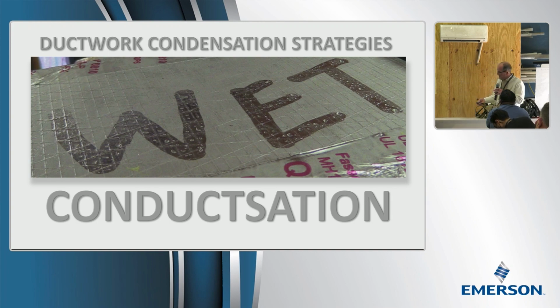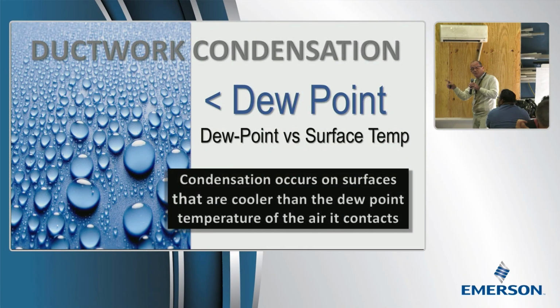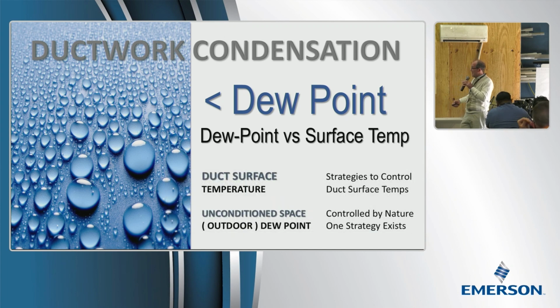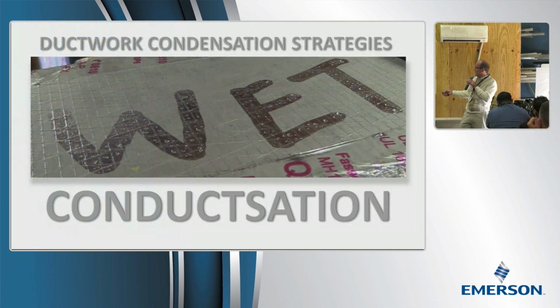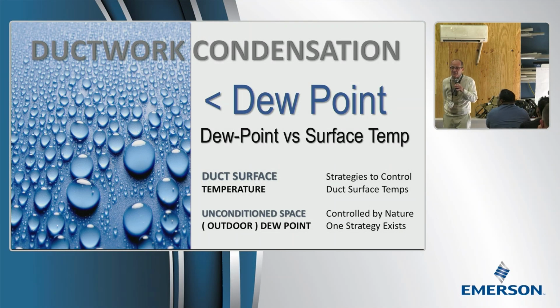This course is all about the dew point versus the surface temperature. We're going to evaluate all kinds of strategies for controlling the surface temperature, because there's so little we can do to control the dew point. What's the strategy to control the dew point? Don't put it outside, don't put it in unconditioned space. If we could put all the ducts in conditioned space at a low dew point, that would solve it.